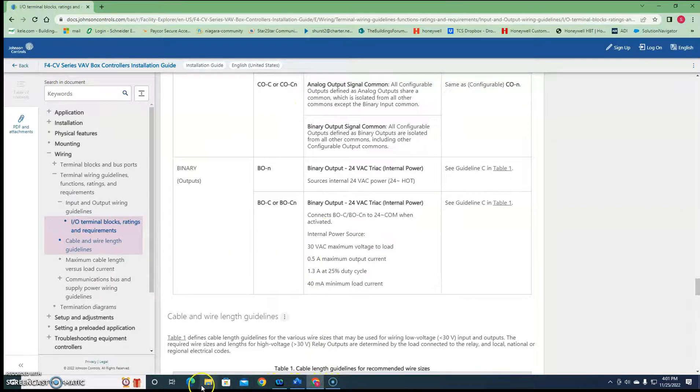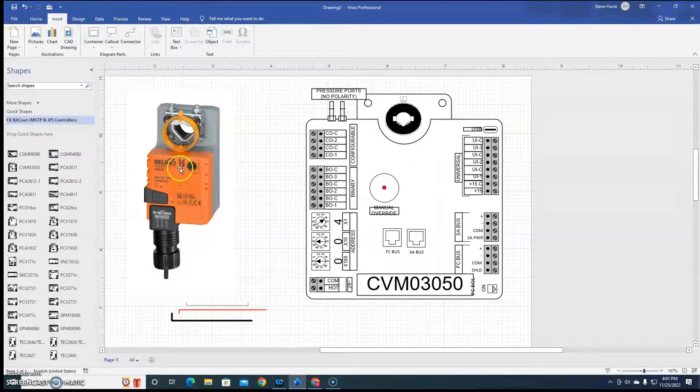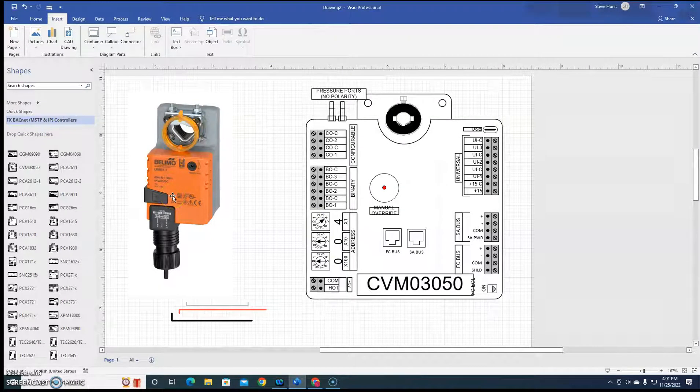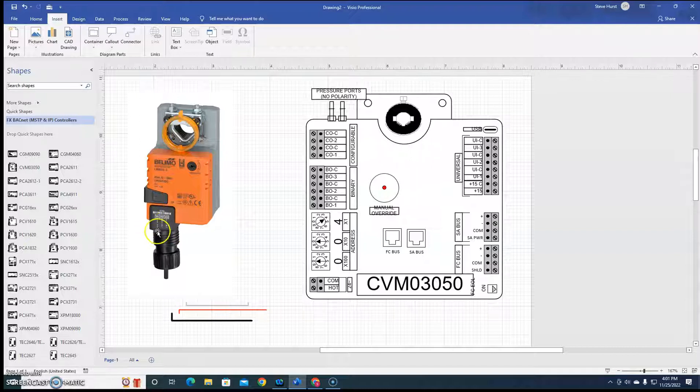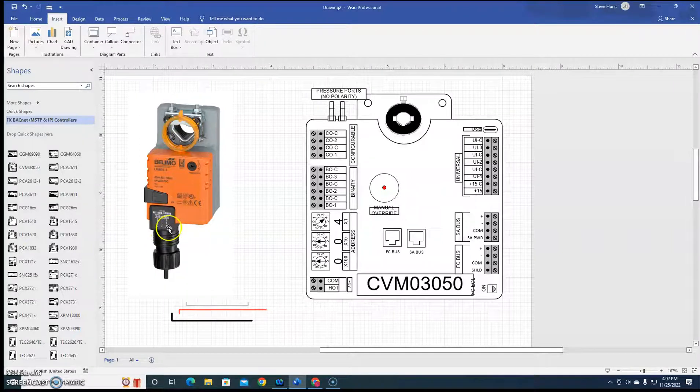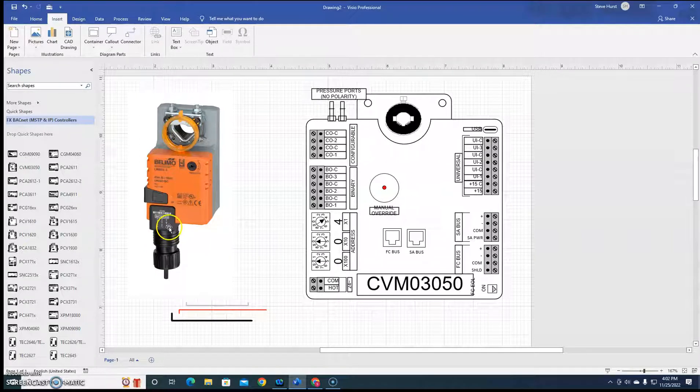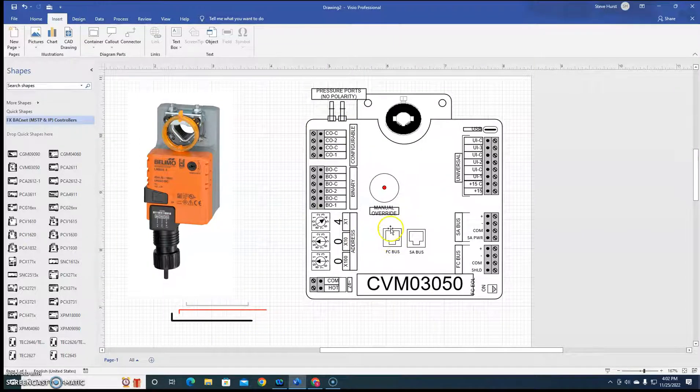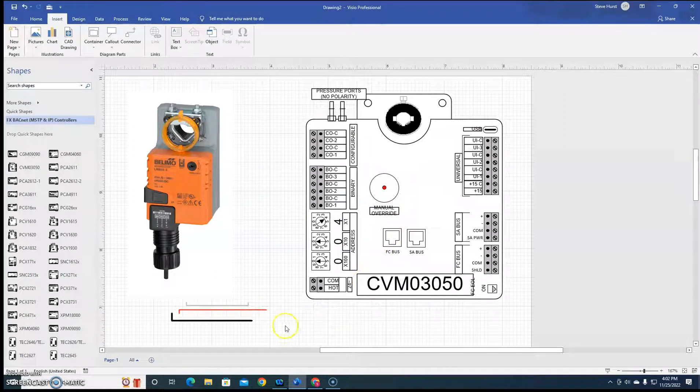So what you do here, see if my Visio is still open. So we have this nice Belimo floating actuator right here. And then we have a black common and then a red to open it and a white to close it. Obviously I can't do white, so I went with gray. So how would we hook this up on the CVM 3050?